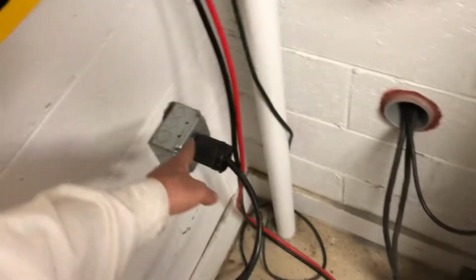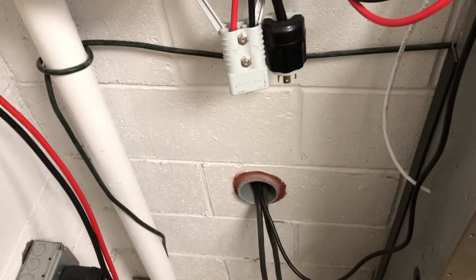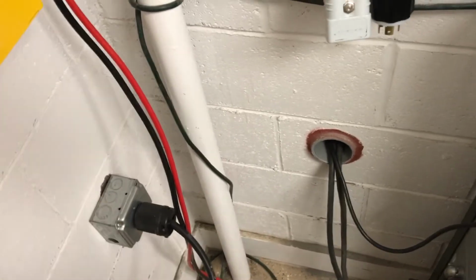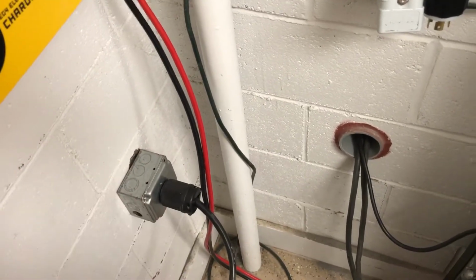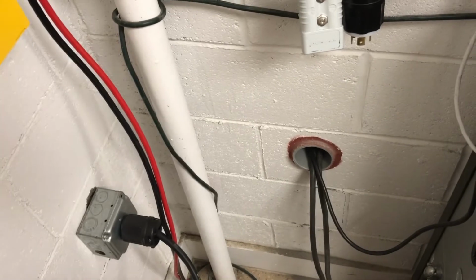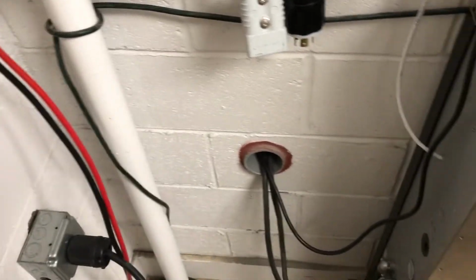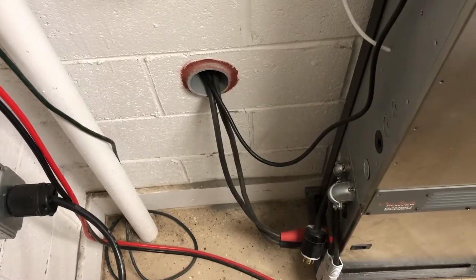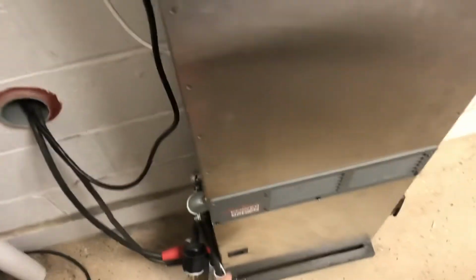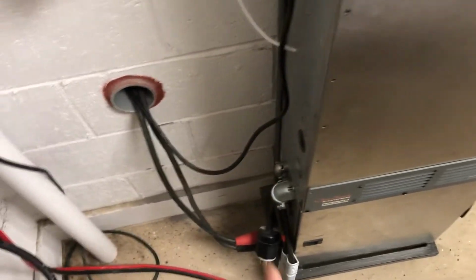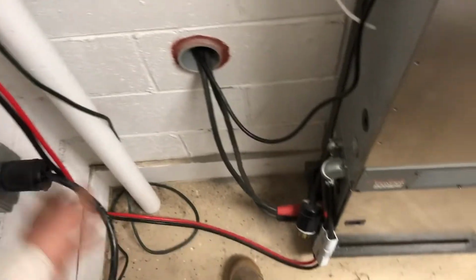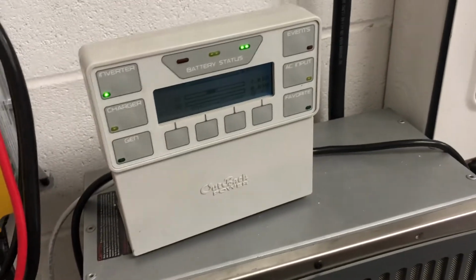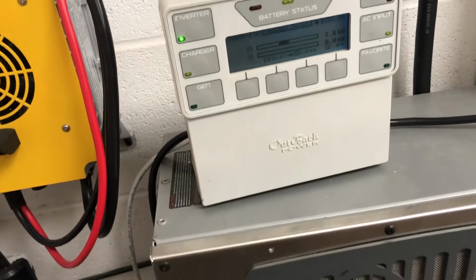Any scenario using the AC input, you wouldn't be able to run AC loads because the maximum capacity of that really long wire is 10 or 12 amps or something. The voltage drop would be too great. This loads panel at the bottom has all the standard connections, and I have an 80 amp circuit breaker on this charger, which is outputting 50 amps. And our loads are working and everything is pretty good.